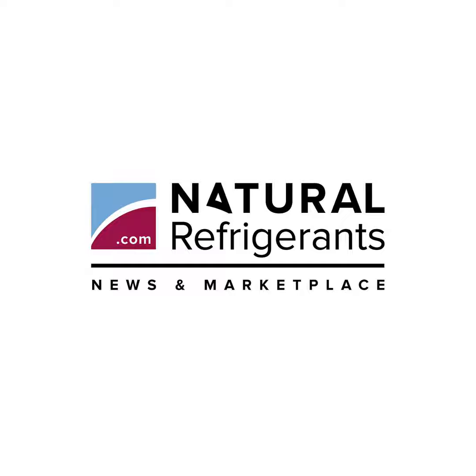INDEE+ Project. The hotel installation was carried out under NTNU's INDEE+ project, an Indo-Norwegian initiative funded by Norway's Ministry of Foreign Affairs. The program aims to demonstrate the feasibility of natural refrigerants in India's HVAC and R sector through real-world applications. Traditionally, Indian hotels have depended on HFC-based chillers for cooling and fossil fuel boilers for hot water in showers, kitchens, and laundry. By contrast, a CO2 heat pump chiller integrates both functions, recovering heat from the cooling process to simultaneously supply hot water, thereby improving overall energy efficiency.